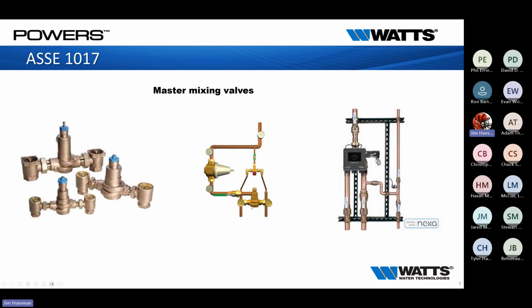And this is just a single high-low - we have our low system, our high system. We're looking at about an hour to really dial it in. But I've done a couple projects - I got pulled into one down in Lexington for UK, and what they had was an actual 6-valve high-low system. Me and my counterpart down there, we had over 5 hours balancing and adjusting.